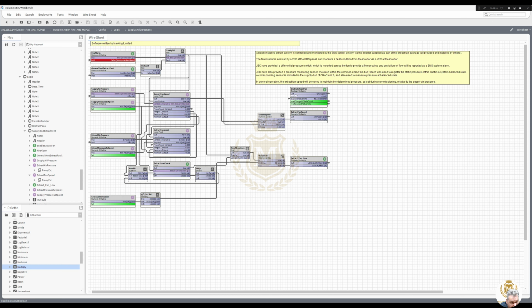And then we need to enable, so we're doing the speed, but we need to enable that, and we want to be enabling it from this supply fan speed, just in case. No, because 40 is going to be on. So regardless of the speed, the fan's always going to be running at minimum at 40, and it's going to be increasing speed. So it's only the fire alarm that actually turns the fan off, which I never mentioned in the des ops here.